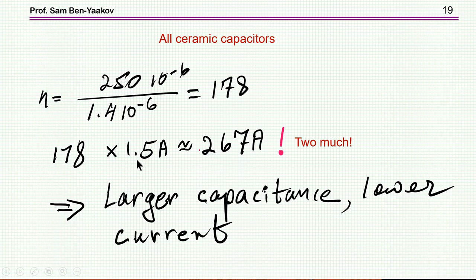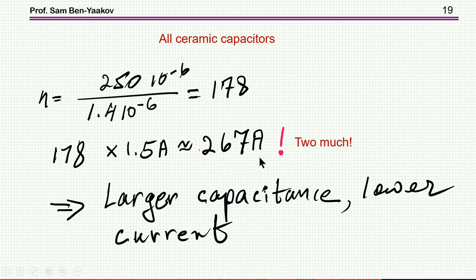The current per capacitor will be 61 divided by 178, so each capacitor carries only a fraction of its maximum. Of course, you can look for a larger capacitance capacitor with lower per-unit current rating, which might be a better choice. There is room to optimize by choosing a capacitor of different capacitance and current-carrying capability.